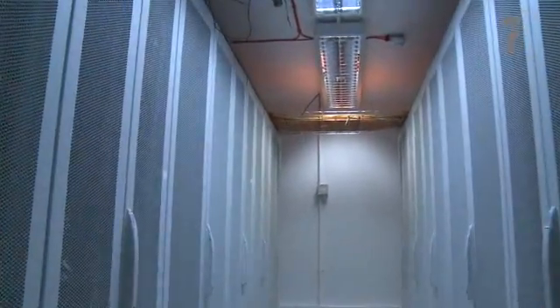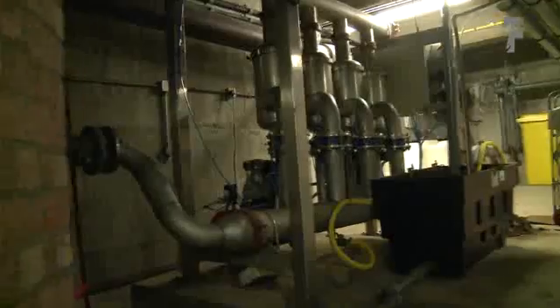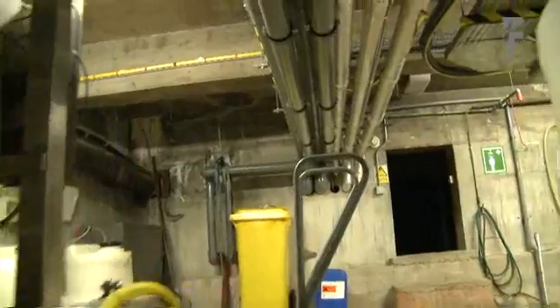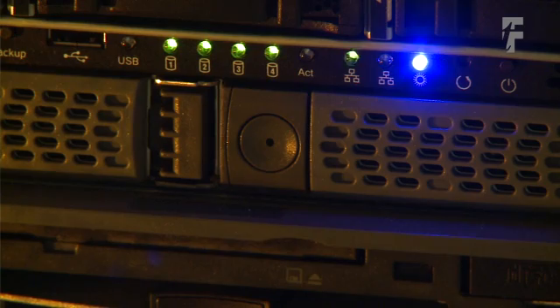Future Tech came up with the ability to listen to what we really wanted and to listen to what things needed to be considered. The data centre design includes power monitoring. We monitor the power going into the data centre right from the power box on the wall. We also monitor the power being used by the servers so we can calculate the PUE quite easily. After a bit of stabilisation we've now got this down to a PUE of 1.16, which is very efficient indeed.